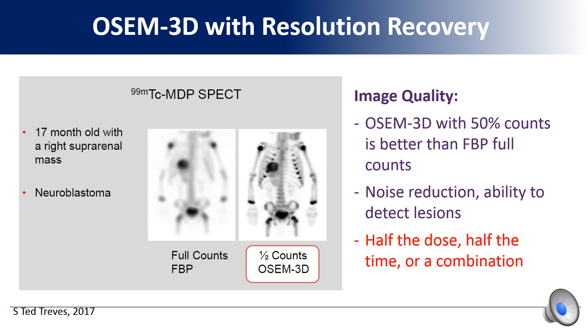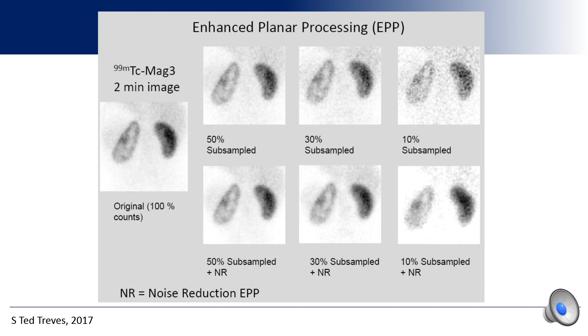This example shows the enhanced planar processing, EPP, used in planar imaging. The first image shows the original image acquired using 100% count for a 2-minute study. Then the count was reduced to 50%, 30%, and 10%. The top panel's images show the images without using noise reduction software, whereas the bottom images show the subsamples with noise reduction software. And you can see even though the count was reduced to only 10%, by applying the EPP noise reduction software, it's possible to filter out the noise and preserve the clinical information.